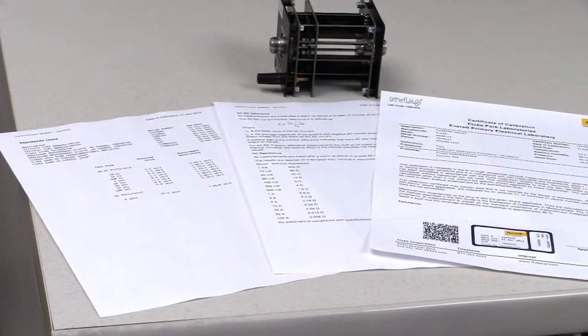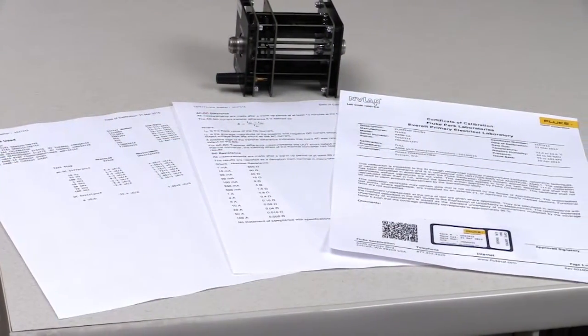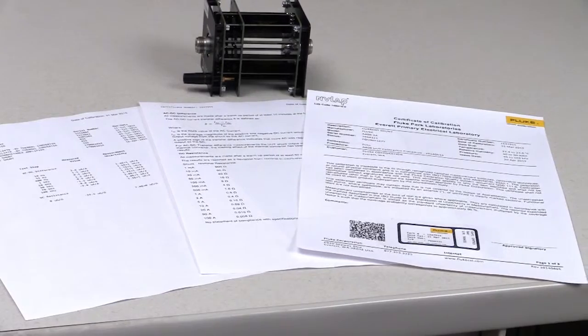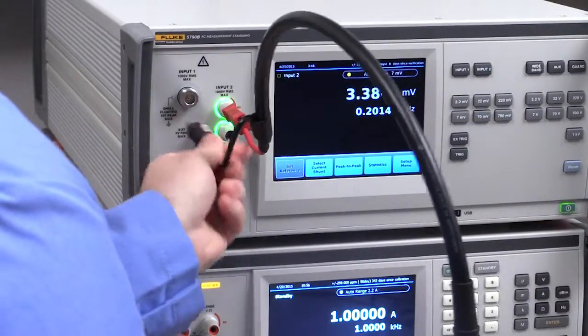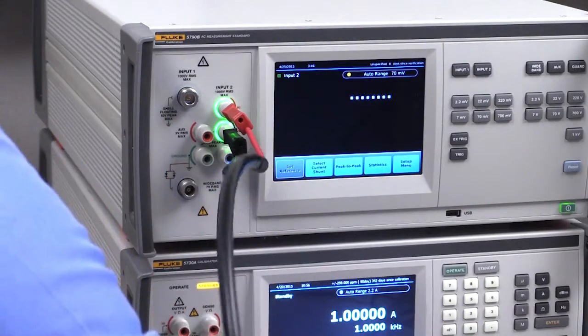Current shunts calibrated at Fluke A40B have a calibration certificate that clearly lists all of the information to load into the 5790B.